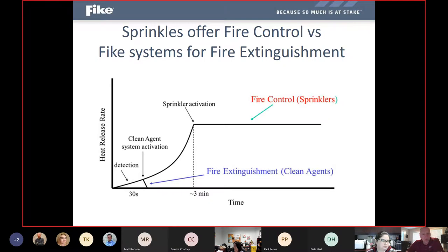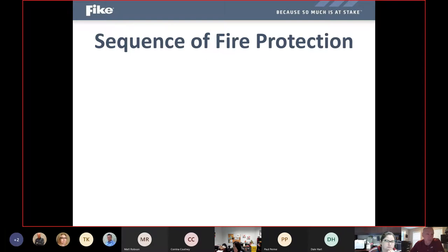The goal of the Fike systems and fire extinguishment with clean agents is not just to control a fire like a sprinkler would, but to try to detect very early, activate the clean agent system to extinguish so that the heat release never gets hot enough to set off a sprinkler. And with the properties and the way that clean agent systems work, we want to minimize the aftermath so that there's really very little cleanup or associated downtime just from the fire suppression system going off. And that's what we're really going to focus on here today, is to show you some of those examples and differences on the clean agent systems as to why people prefer them in certain areas.